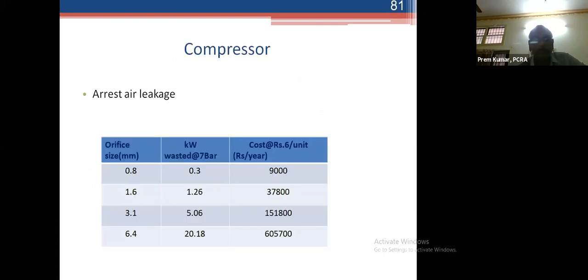So one company wanted to quantify it. The company was working 5,000 hours, 2 shifts in a year. The most preferred size was 6.4, a very popular size. They wanted to find out if the leaks go unnoticed, unattended. The company was spending 6 rupees per unit. So the wastage will result in around 6 lakh rupees. Today the cost is close to 8 rupees. The pressure used was around 7 bar. You can imagine the cost.